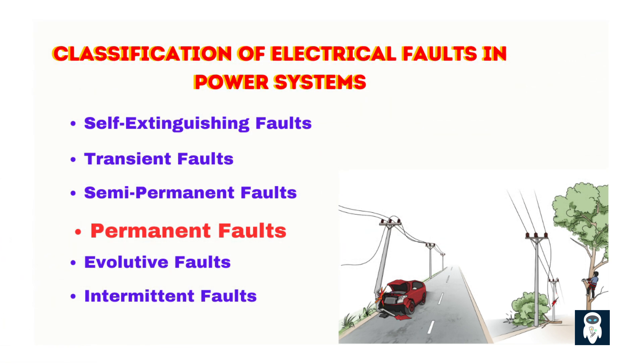Permanent faults cause significant disruption and cannot be resolved automatically — they require manual intervention by operators to restore service. These are persistent faults that result in physical damage to infrastructure, where protection systems isolate the faulted section but service restoration requires repairs. Examples include underground cable damage from excavation equipment cutting cables, and storm damage such as broken poles or conductor severance due to high winds, resulting in prolonged outages and high maintenance and restoration costs.